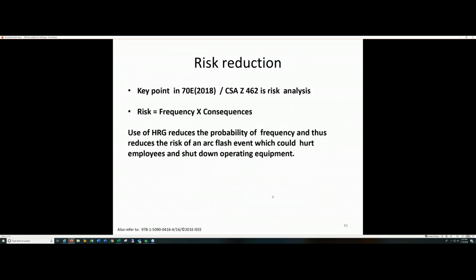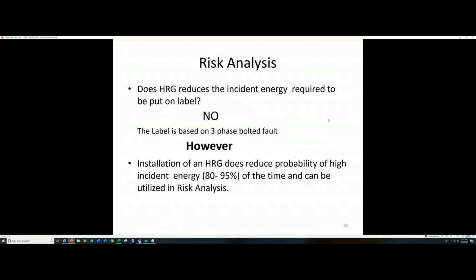Well, the key point in 70E 2018 and 462 is let's reduce the risk. Risk is equal to frequency times your consequences. If that's the case, the use of HRG does in fact reduce the probability of frequency, and thus reduces the risk of an arc flash event, which could hurt employees and shut down operating equipment. So that's real important. Deploying an HRG sounds kind of odd, you're putting in a higher resistance, but in fact it actually helps. It helps tremendously with employee safety, and it helps tremendously with maintaining equipment and being able to have orderly shutdowns when you have a fault. And it's not taking you down, like I said, at Friday afternoon at 5 o'clock or at 2 a.m. in the morning.